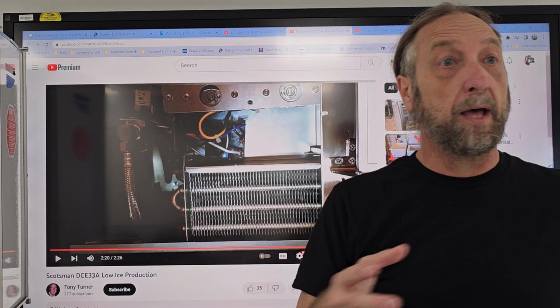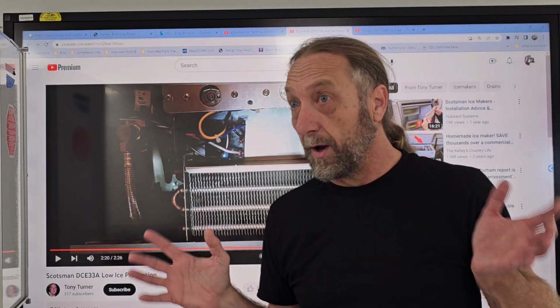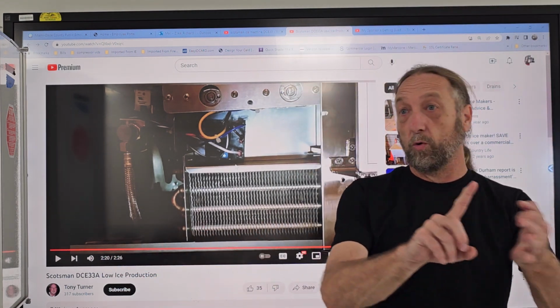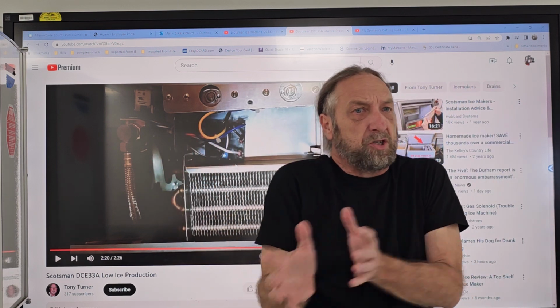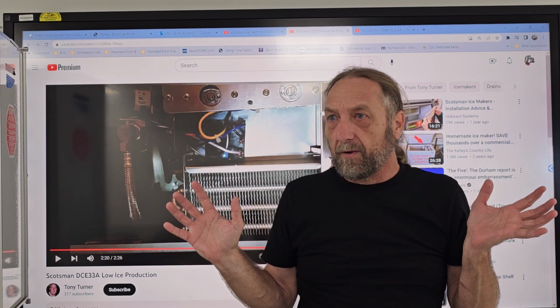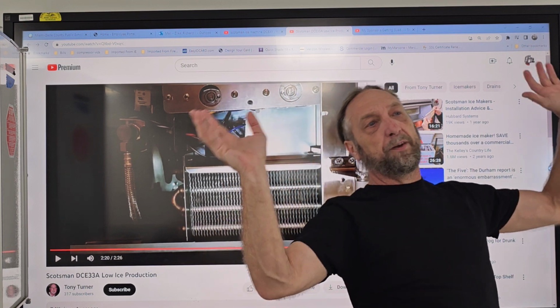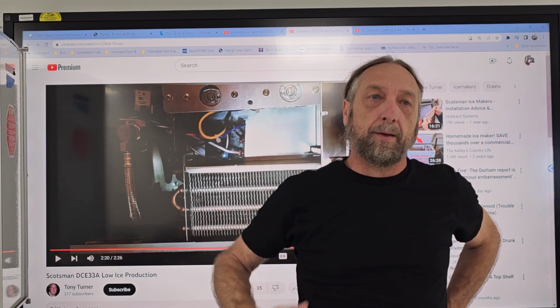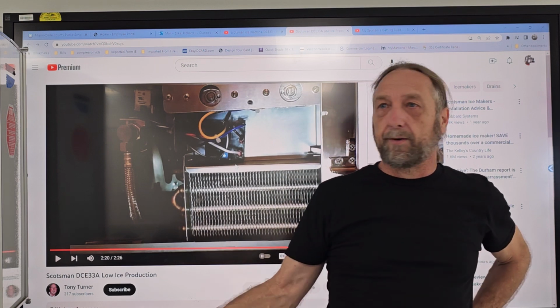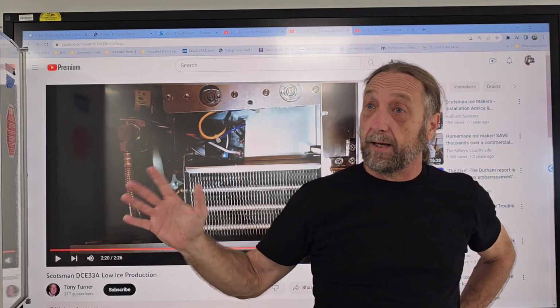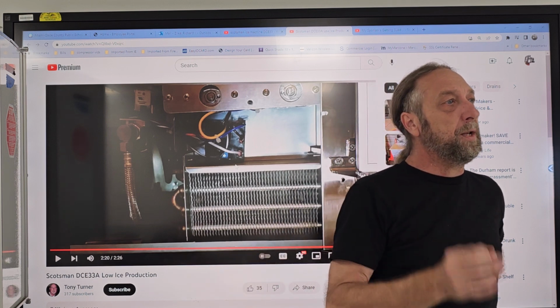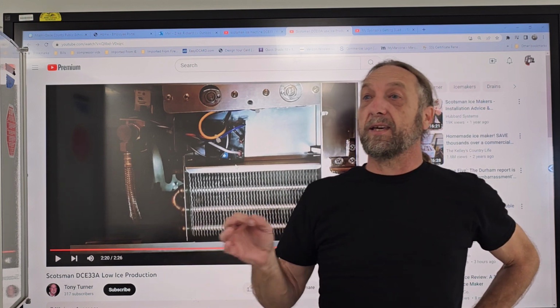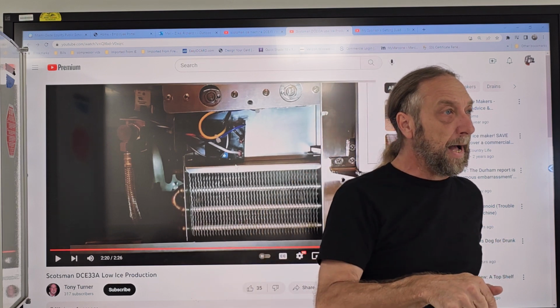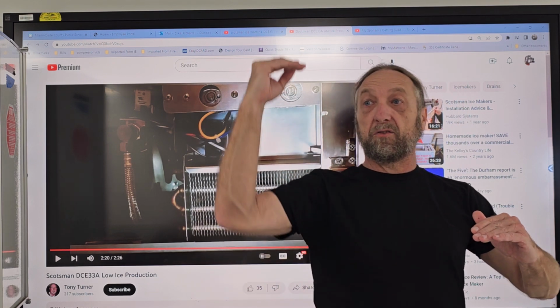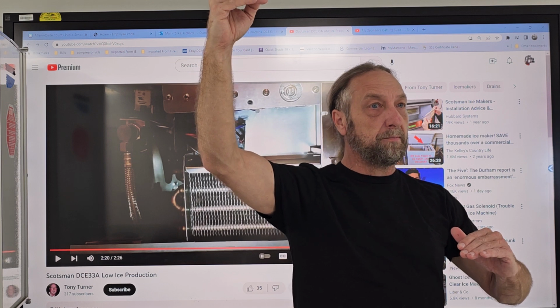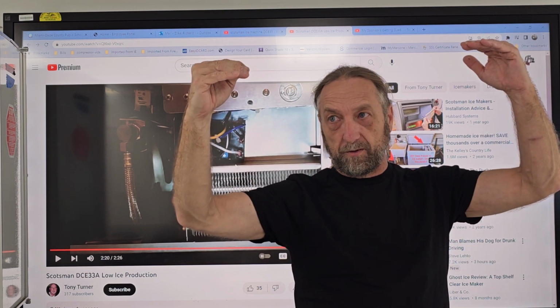It's important, the right temperature and the right pressure, or we're not gonna get refrigeration, cooling, ice machine, whatever you wanna say. This is just a refrigerator. That's all it is. I don't look at it as like, oh, it's an ice machine. I fix refrigerators all day, but it's an ice machine. Except for the electrical circuitry, it's got a compressor, evaporator, condenser, just like any other system. But we need to release the heat. If we don't release the heat, the compressor running hot, heat is going to raise what? If I have more heat, what am I going to raise? Pressure.